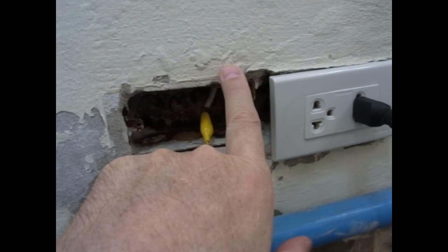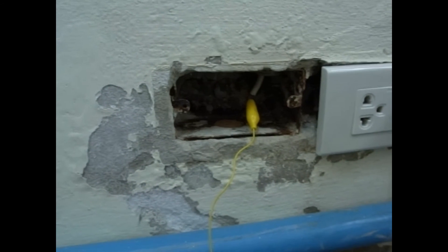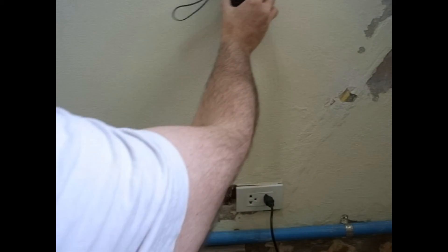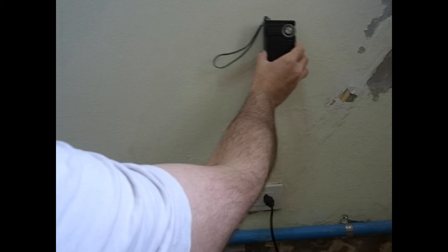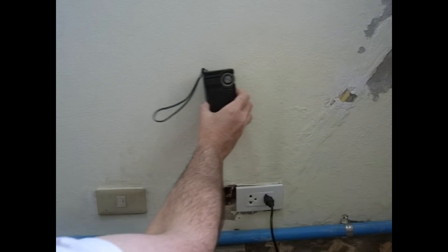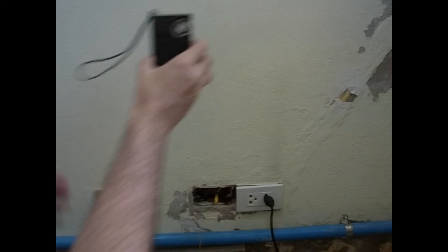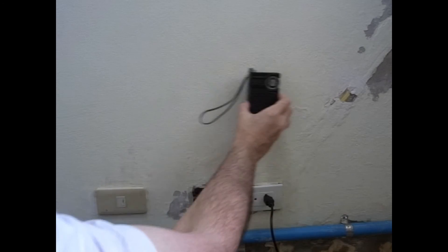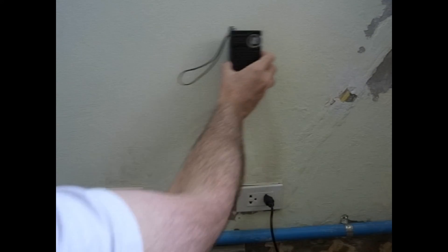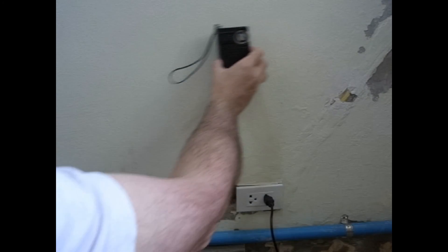You can see the conduit going up here — it's right about here on the box, so let's see if it will follow it. We got her tuned up — let's listen. Yep, there's the conduit right there. As I pass over it you can hear the signal rise. So there's my conduit running up there. Now somewhere up higher it bends, and that's what I'm going to go looking for.